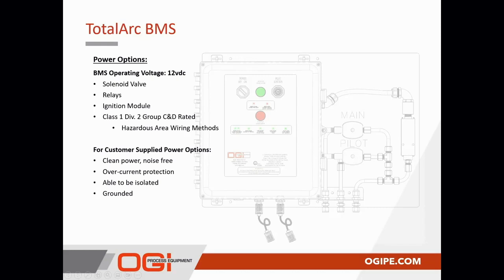The power source selected will impact the ability for the BMS to support itself when primary power is lost. So basically, the longevity of that loss of power and how long that BMS can continue to operate normally without the primary power being available. And also the customer field interconnections required will also vary based on the specific BMS power source selected.